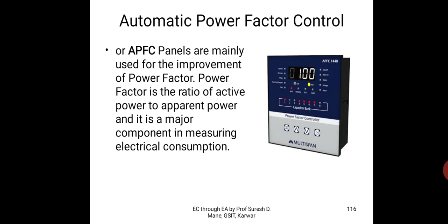Then maximum demand controller. As I told, if you exceed the contract demand with the DISCOM, the distributor company, you have to pay a penalty. The DISCOMs differ by region, for example Hubli Electricity Supply Company, Chamundeshwari Electrical Supply Company, BESCOM and so on. That is why people are using a maximum demand controller, so that if the demand is exceeded, the non-essential loads will be cut off automatically. So this is known as a maximum demand controller, so that the demand of your industry or organization remains within the contract demand you have with the electrical supply company, that is the DISCOM.